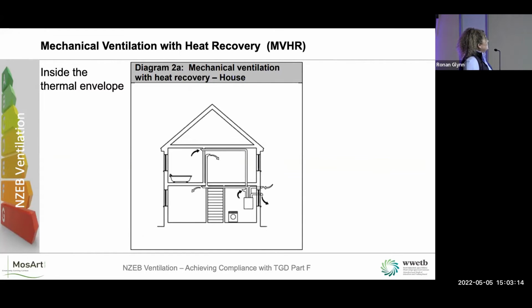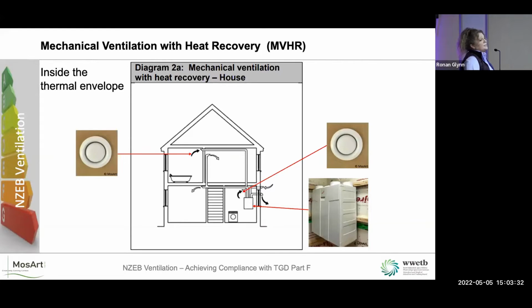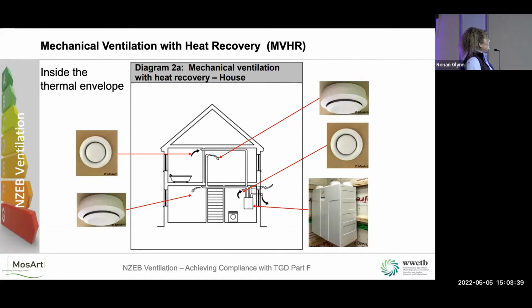So this is mechanical ventilation with heat recovery, our MVHR. We suggest, now it's not a requirement for NZEB, but it is definitely a recommendation that you put it inside the thermal envelope. So we have our centralized little unit here down in our utility room. We have diffusers for extract, similar to our CMEV, but now we have diffusers for supply. So we've no background ventilators and we have a relatively airtight house. If we keep it down inside our thermal envelope, inside our airtight membrane, then we don't have any perforations in it. We've only got one that comes in, so your intake and your exhaust are the only two that breach your airtight membrane and your continuous insulation.